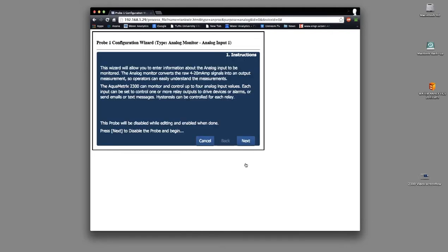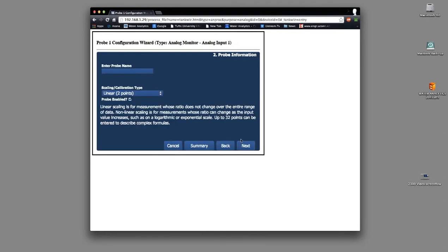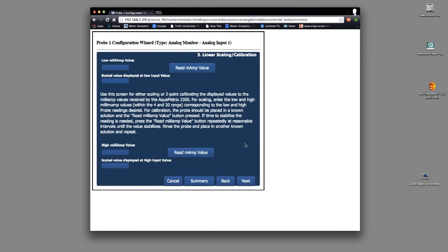The next screen gives us an idea of what's in store for us as we set up and calibrate the probe and set up alarms and relays. First, I'm going to give it a name. I'm going to call this probe Demo PH Probe. I'm going to calibrate it using 2 pH calibration standards. So I'll choose linear, 2 points for the calibration type. Click Next, and the next screen is where all the fun begins.